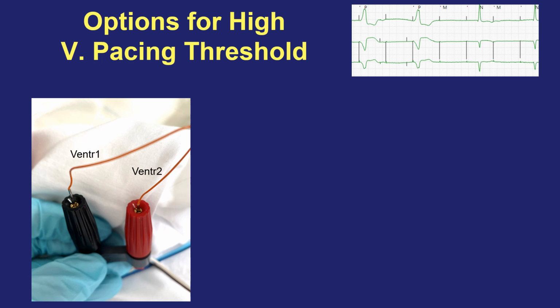So one option that you have is you can switch these two electrodes and use the one that was the anode as the cathode. Maybe that wire is the better of the two wires. Maybe there's less inflammation. You can potentially lower the pacing threshold. You have a 50-50 chance one wire is better than the other. And if you're already losing capture with the way it's set up, you can quickly unscrew each of these and do a really quick change around and switch them out. Remember which is which, of course, and see, you might have a better pacing threshold. Maybe you're losing capture at 20 milliamps in one way, but you drop it down to 12 milliamps in the other way, and that gives you a little bit of extra time to come up with an alternative pacing option.